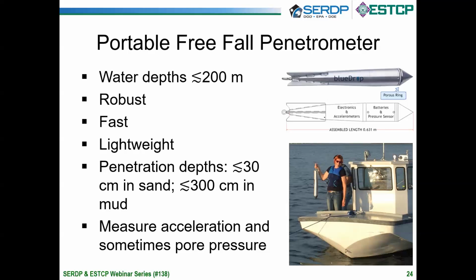The deployment is very fast. It falls typically with velocities of 4 to 6 meters per second through the water column. So you can imagine, depending on what your water depth is, your deployment may be less than a minute, including bringing it back up. And then often, because it is so fast, we actually deploy it 2 or 3 times in the same location to also assess how much small scale spatial variability we have here.